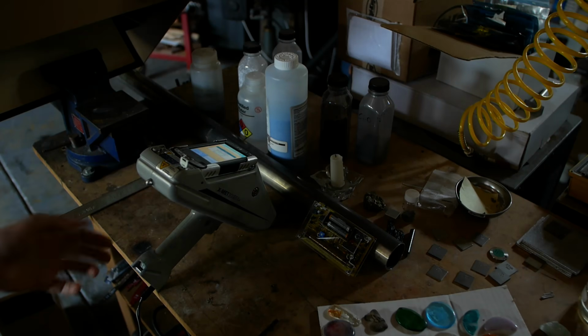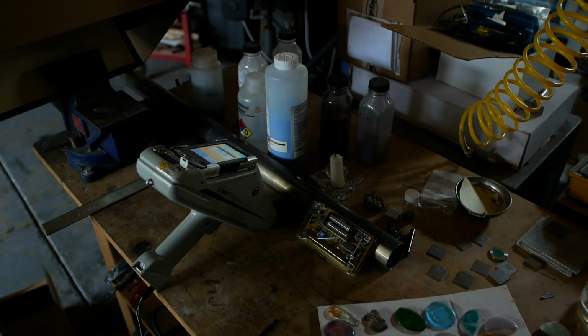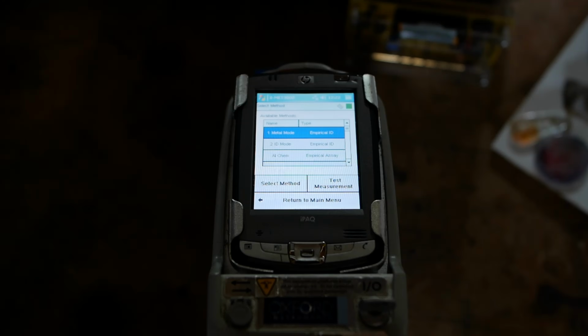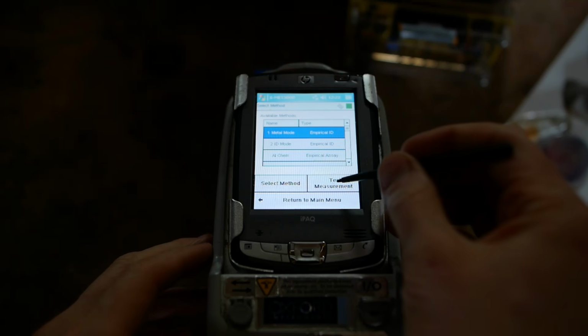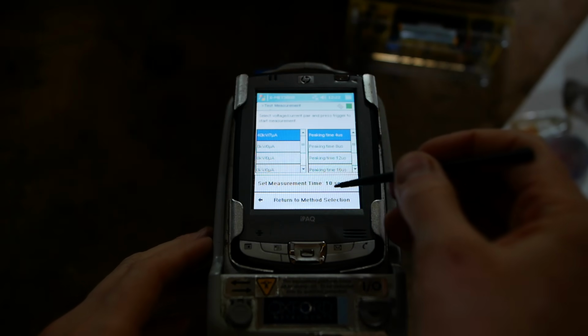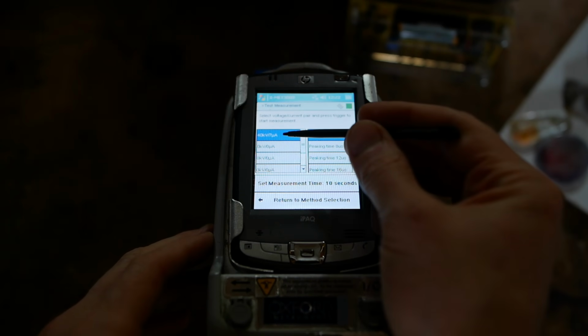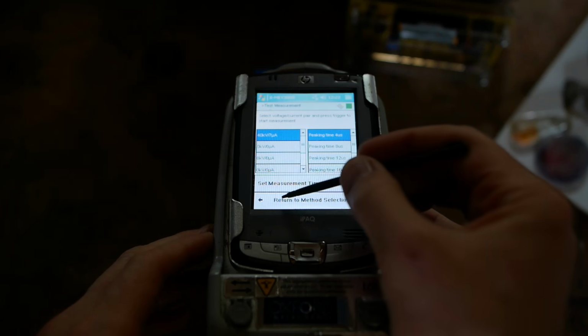So you can see it does trigger the Geiger counter, but it's actually not as intense as even some radiation check samples that you can get. This software is configured to emit 7 microamps at 40 kilovolts. So again, that's 10 or 100,000 times less than a medical imaging tube. I'm going to try to set this up in a dark box here with a fluorescent screen so you can get a sense of how big the X-ray spot is.